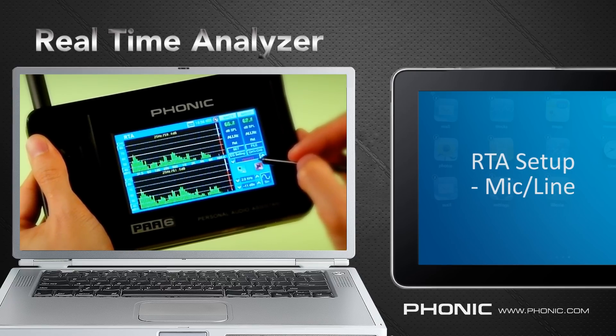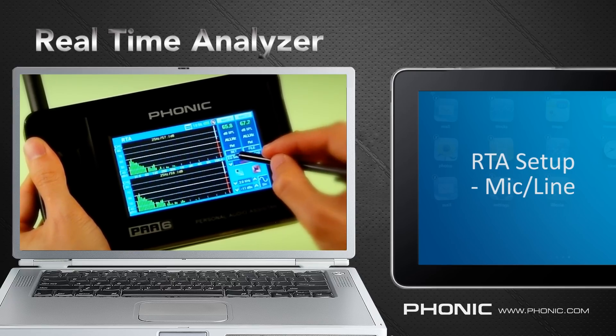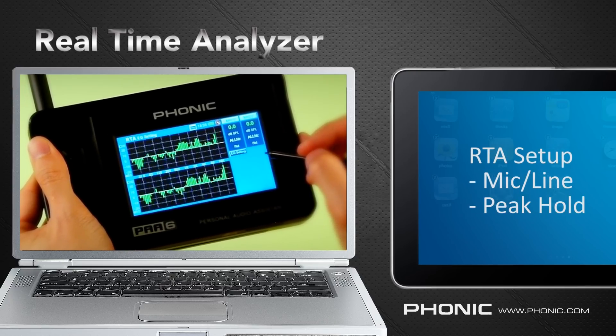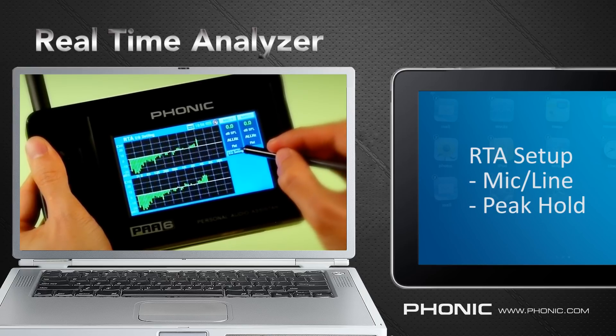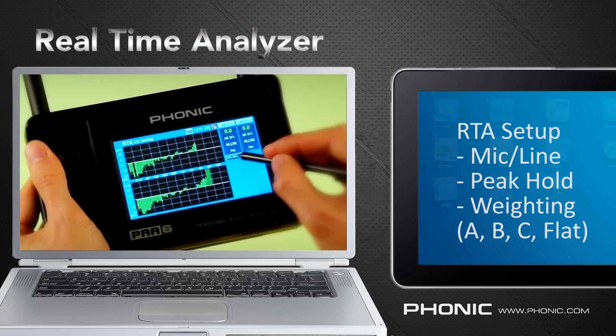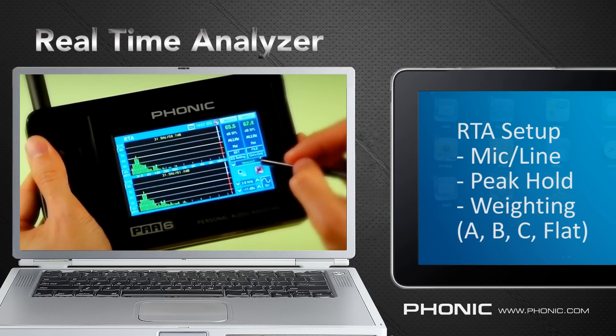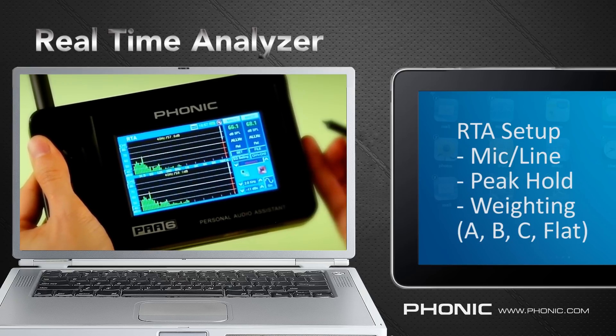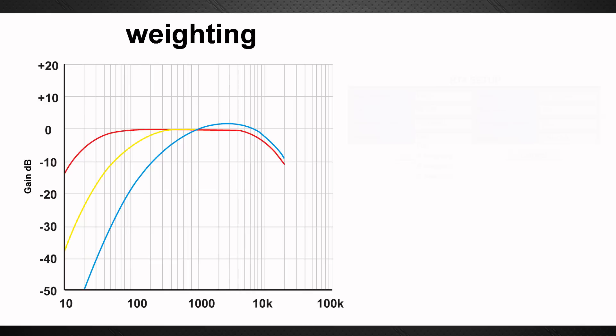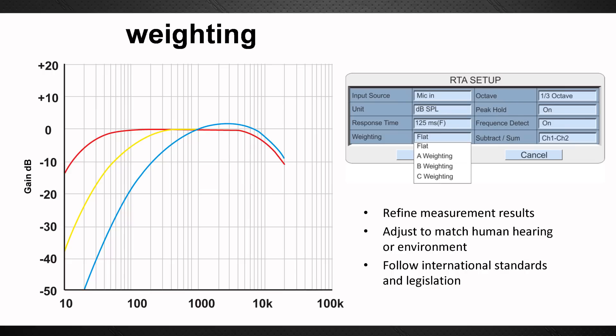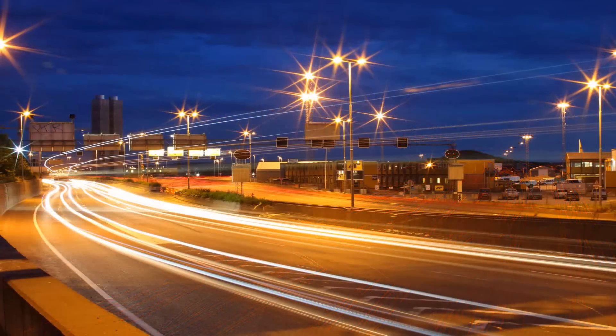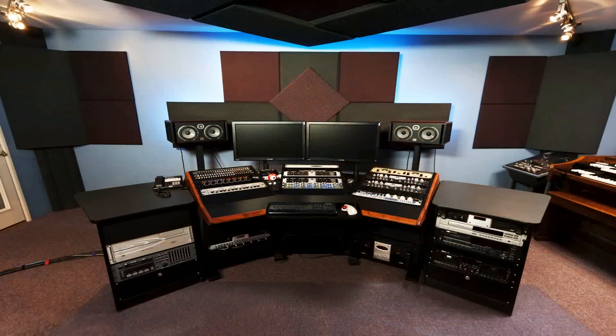You can select whether you want to use microphone or line input, whether there's a peak hold time, and most importantly you can select the weighting. There is A, B, C and flat weighting available. To understand weighting you need to understand that human hearing has a particular frequency curve and that some frequencies we can hear better than others. The weighting helps the analyzer understand this and provide us with results relevant to our hearing range.